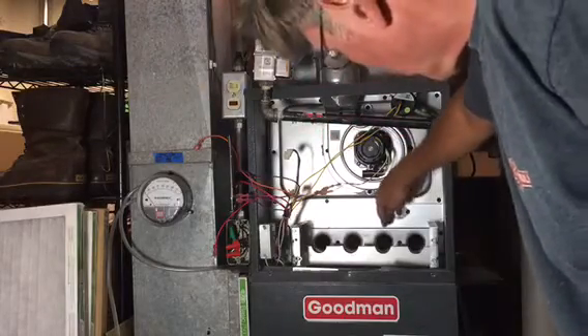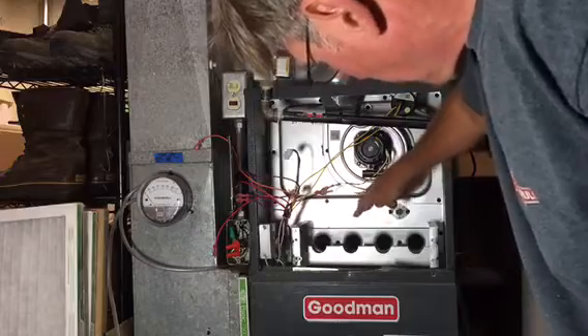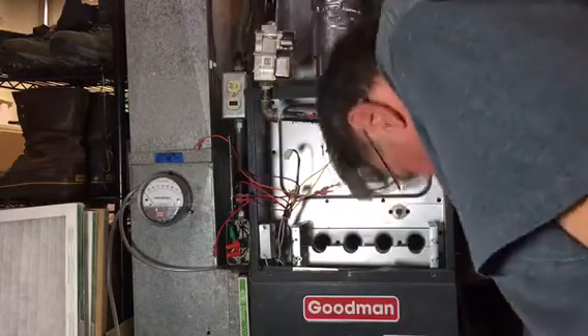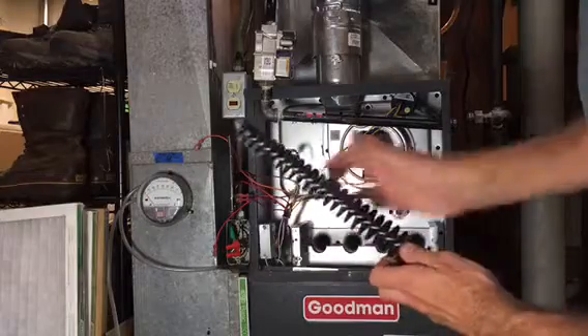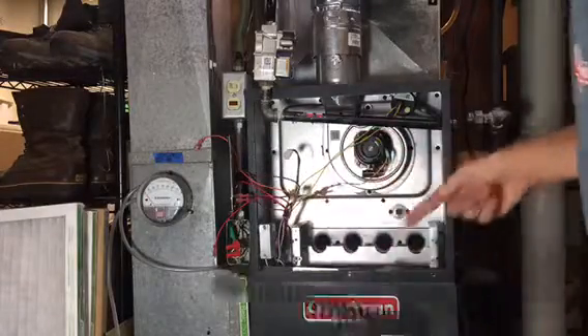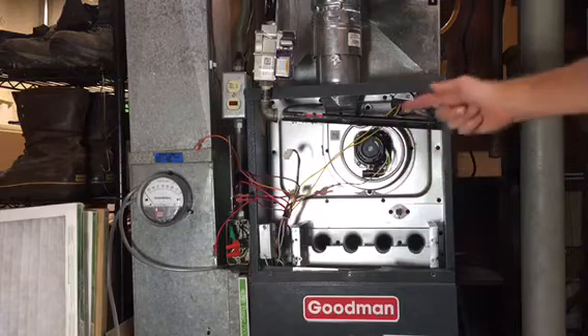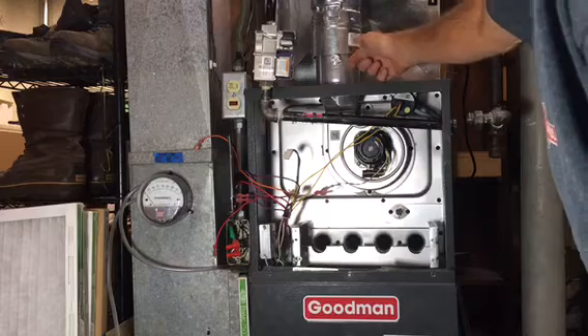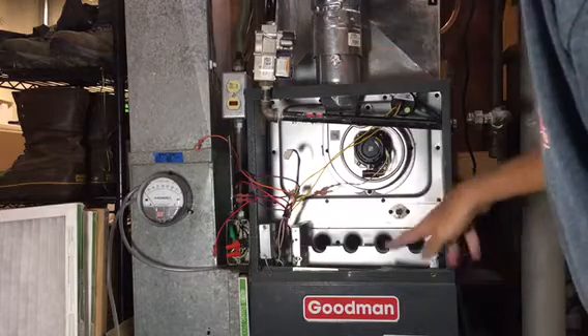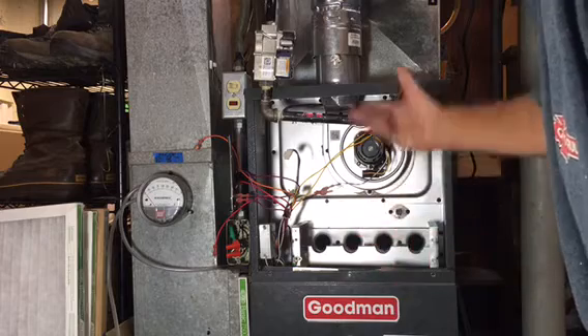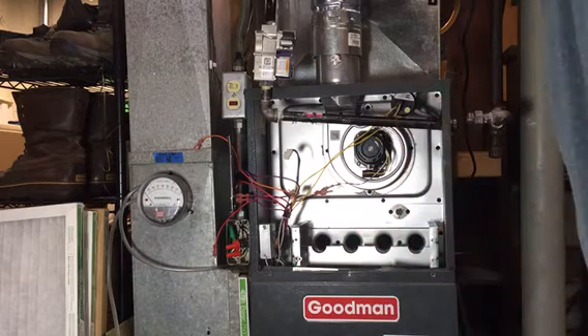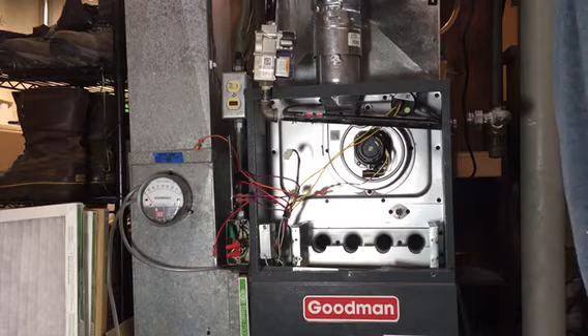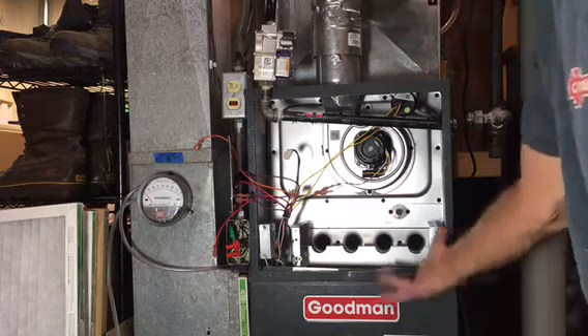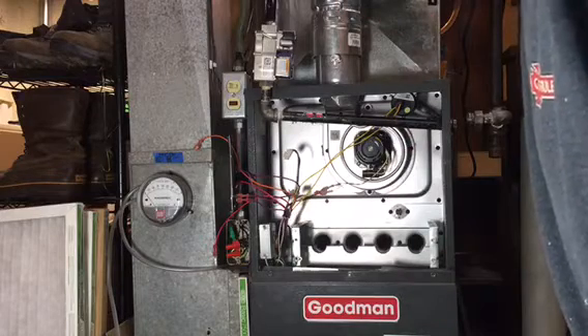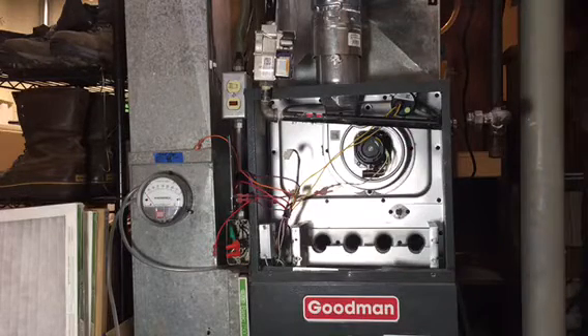Now we're going to take a look inside the heat exchanger tubes themselves. You want to make sure there's no corrosion. If there's any debris, we've got an extended brush here that we can loosen that with and then vacuum it out. And the heat exchanger basically are these tubes, 4 of them that curve back and forth and end up exiting right here at the vent. The flame shoots inside the tubes and the air circulates on the outside of the tube separate. And that's what heats your house. That makes the makeup air as it flows through from the blower down below. So let's see if we can take a peek in there and see what those look like.